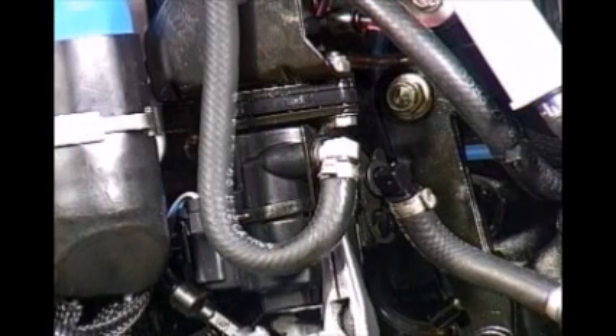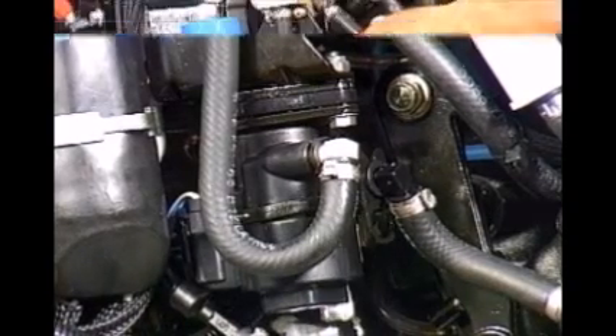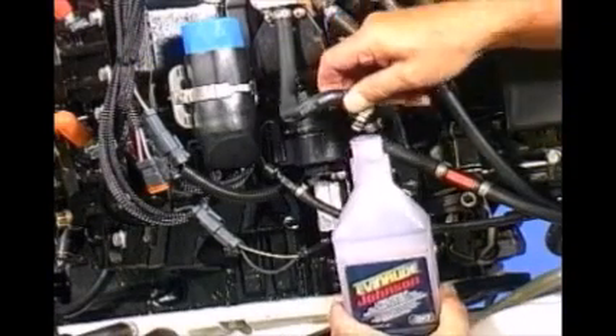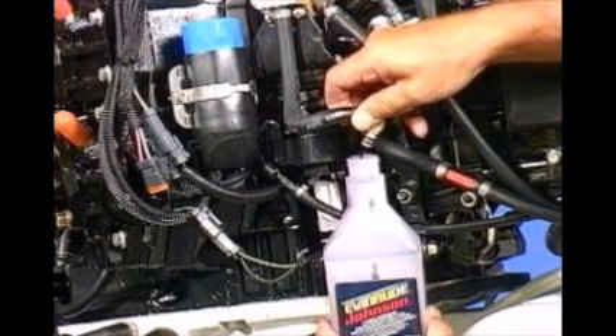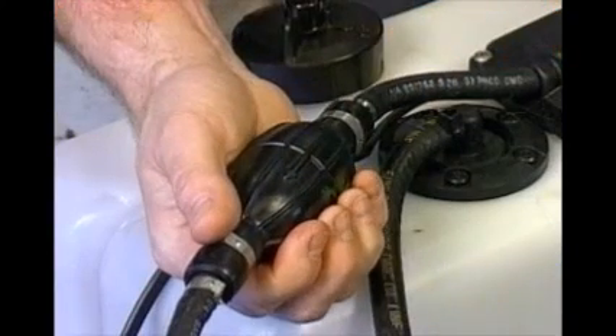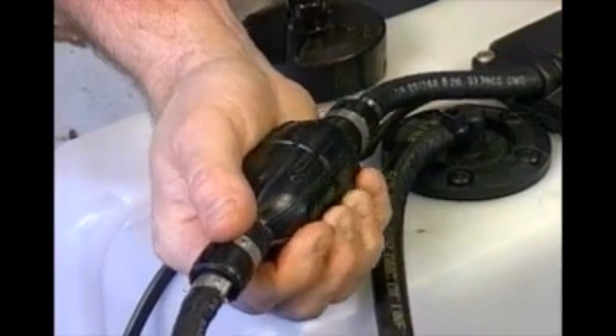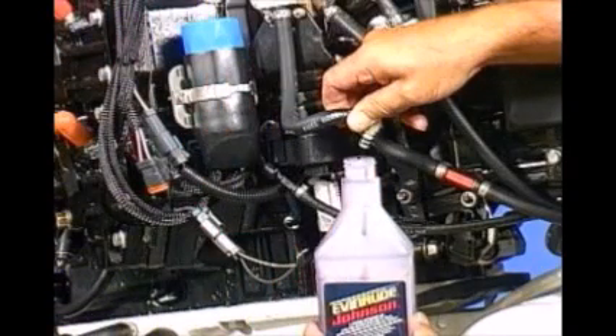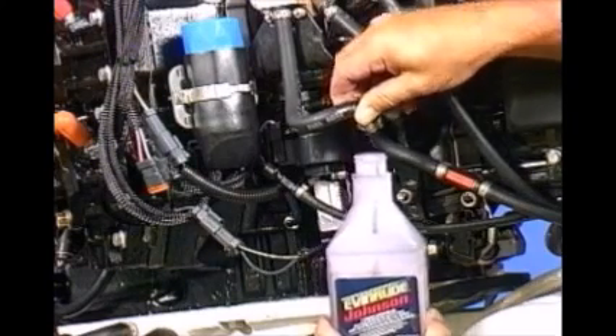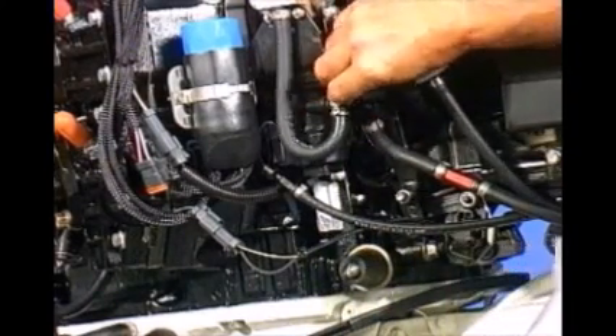To purge the oil system on direct injection models, remove the inlet oil fitting from the oil injector and use a suitable container to catch the oil. Squeeze the oil supply primer bulb until oil flows without any air bubbles. Reinstall the inlet oil line.